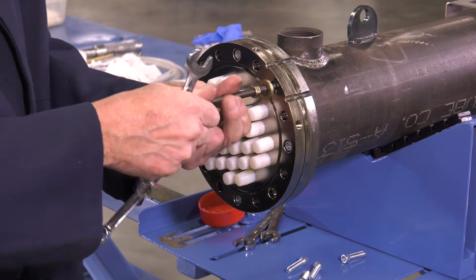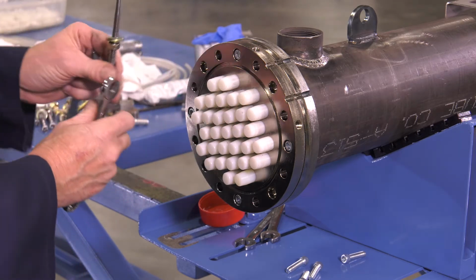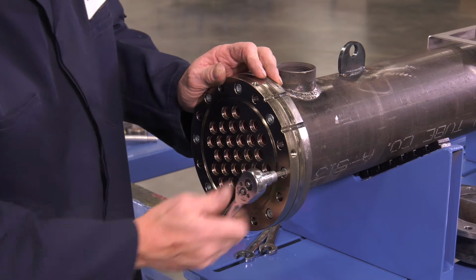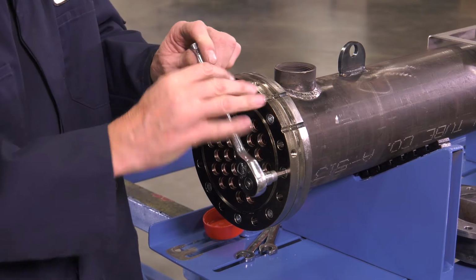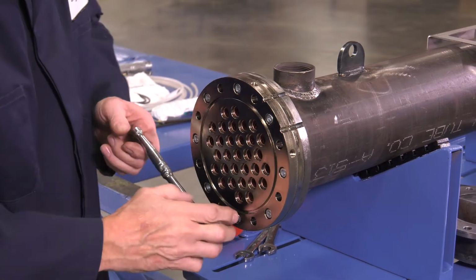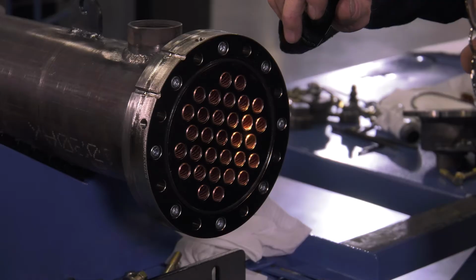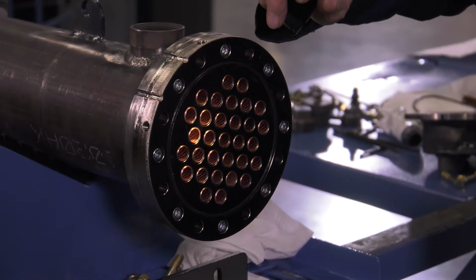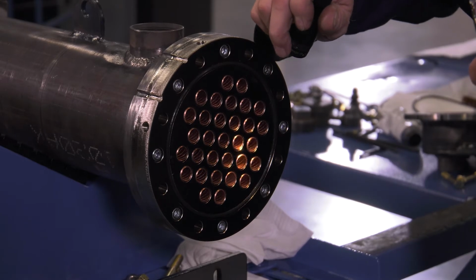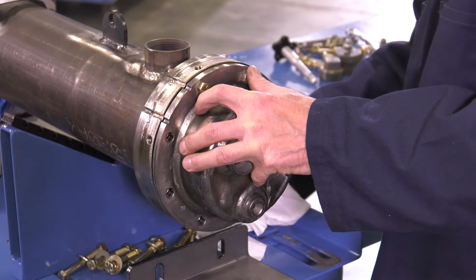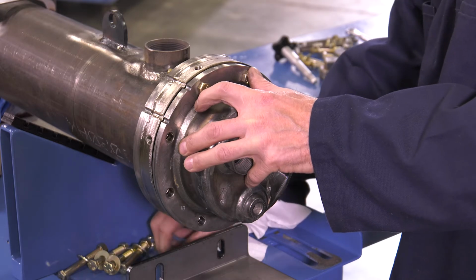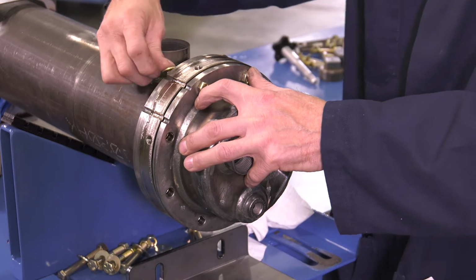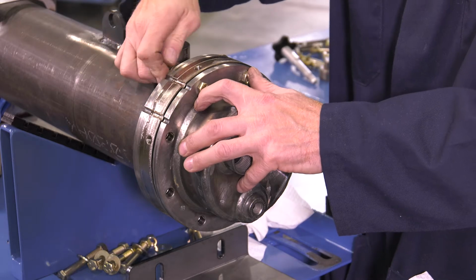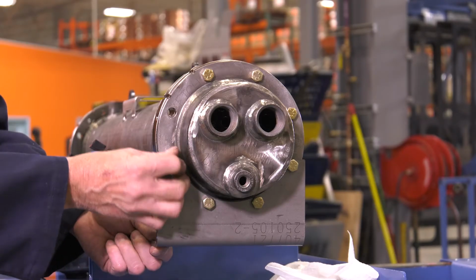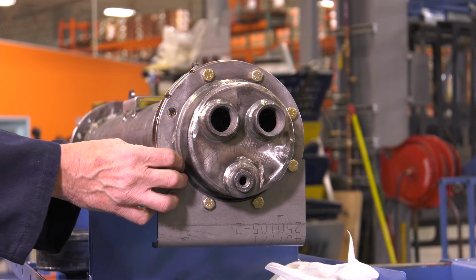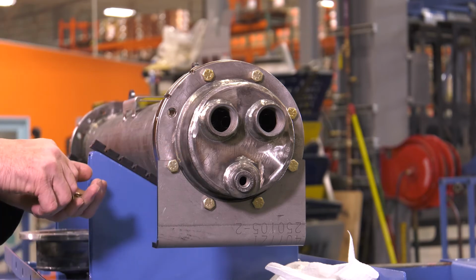Remove header plate draw-down bolts and plastic assembly bullets. Install proper header retainer bolts and torque both headers as recommended in the System Protector Service Manual. Inspect tube holes for remnants of torn rubber seals. If necessary, replace damaged seals. Install the tank ends, ensuring to line up the orientation notches. Insert bolts, flat washers, nuts. Install the mounting feet in the same orientation as they were removed on each end and tighten.